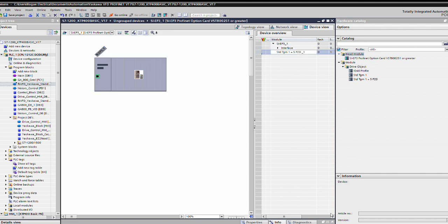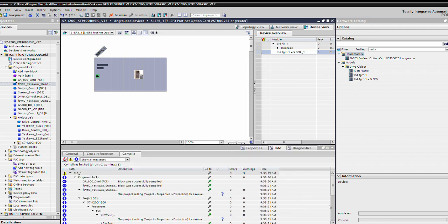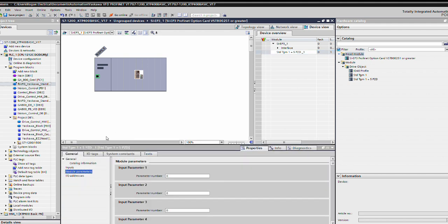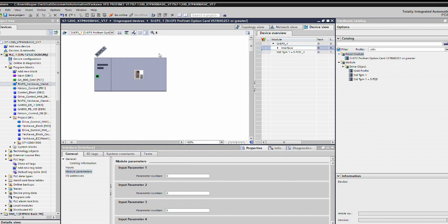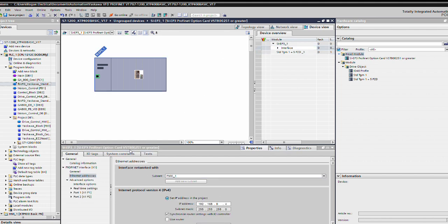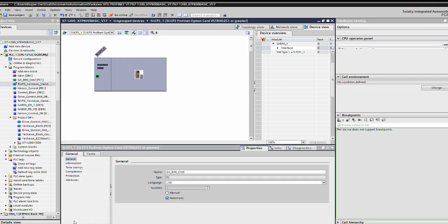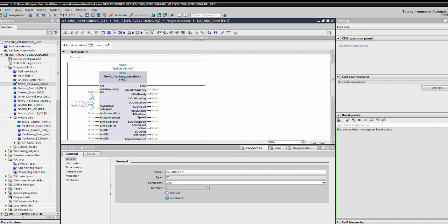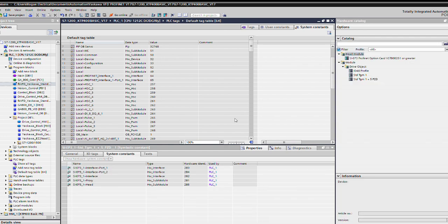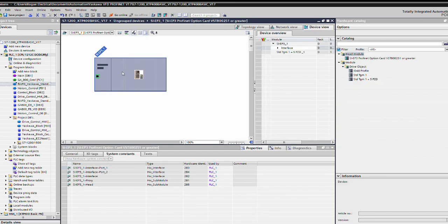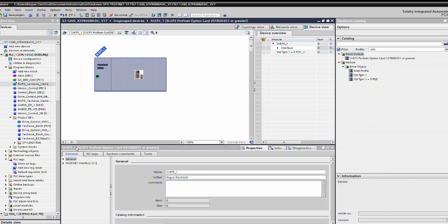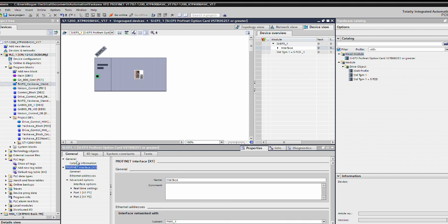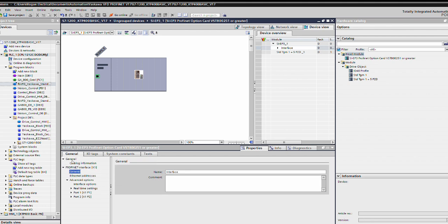Once again, we're going to confirm that we do in fact have the right drive selected, because you know you could be dealing with multiple. Where's your interface? Yep. IP address, system constants. And there it is. 283 to 285, and over here 286. There's your command bit. Good deal. So we're going to go over to your Yaskawa interface. Going to go to general ProfiNet. I'm going to get to the module.